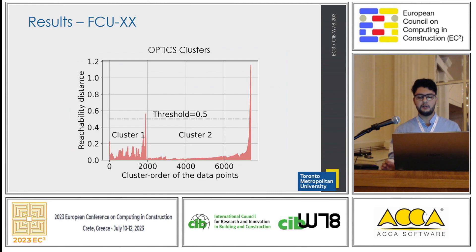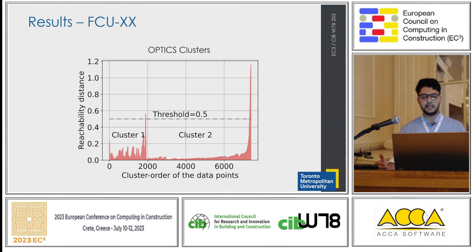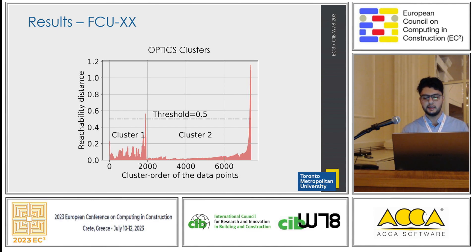Here we see the output of OPTICS clustering. Unlike most other clustering algorithms that directly group data points into clusters, the output from OPTICS is a list of ordered data points with respect to reachability distance, allowing for visualization and cluster identification. The valleys under the threshold, separated by the intersection of the threshold and the reachability distance, indicate the existence of a cluster. For fault detection, we can consider a threshold of 0.5 for this example to have just two clusters — normal and faulty. Or we can decrease the threshold to have more clusters to check for the presence of multiple faults using the temporal distribution of identified clusters.